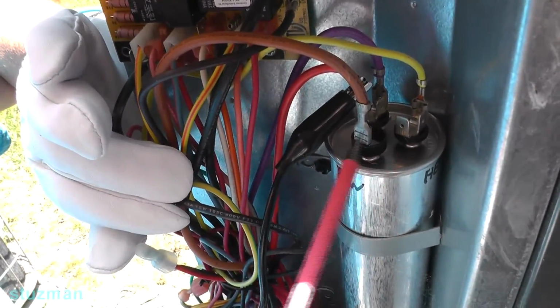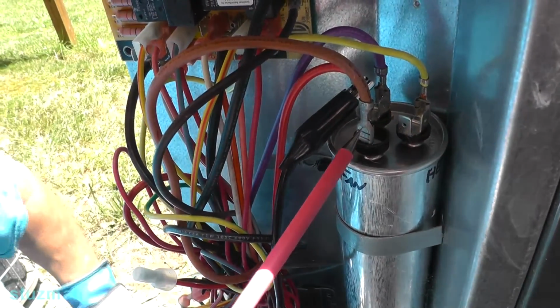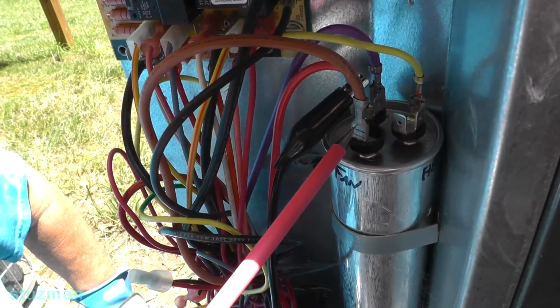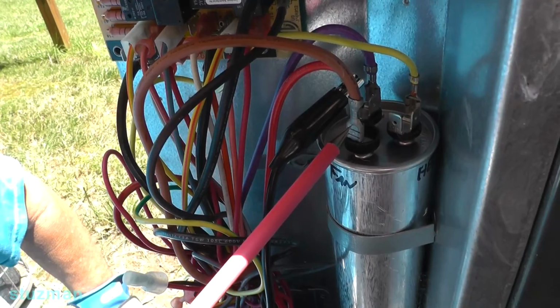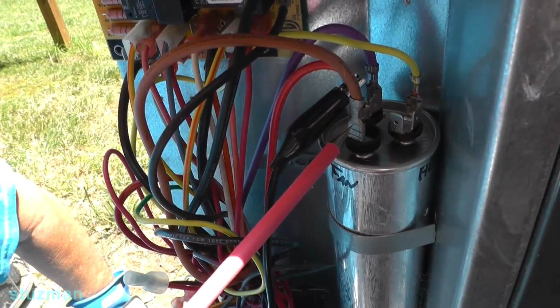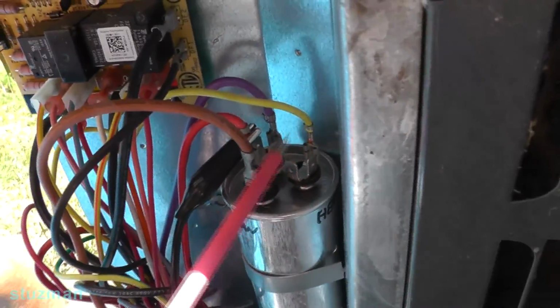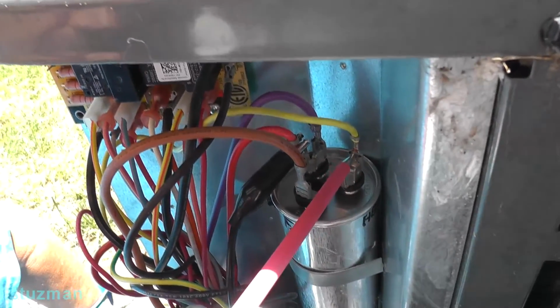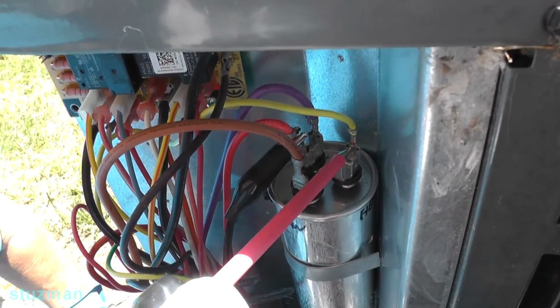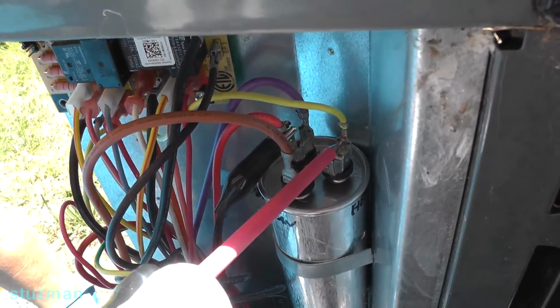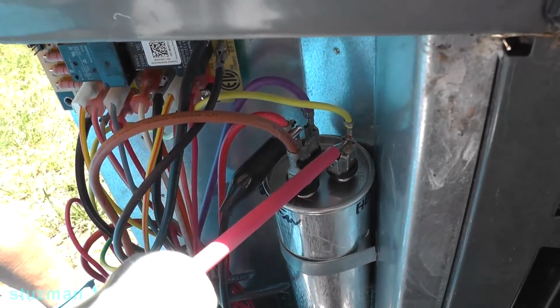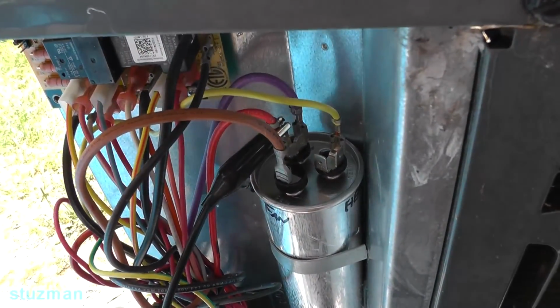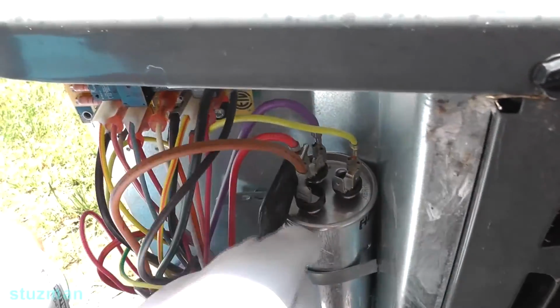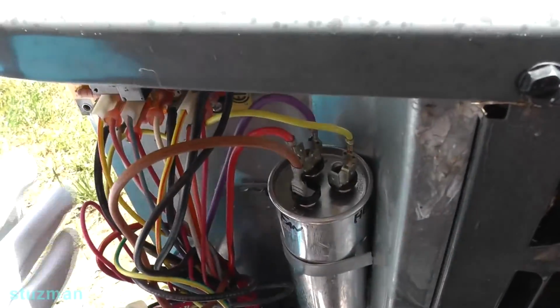So now I'm going to put it on, say, the fan. So I put it on there and I'm going to count 1001, 1002, 1003, 1004, 1005. Now that capacitor should be discharged. Now I'm going to go back here to the one for the compressor. I'm going to hit it, 1001, 1002, 1003, 1004, 1005. And now that one should be discharged. So now we should be safe to pull the wires off and not have to worry about getting a shock.